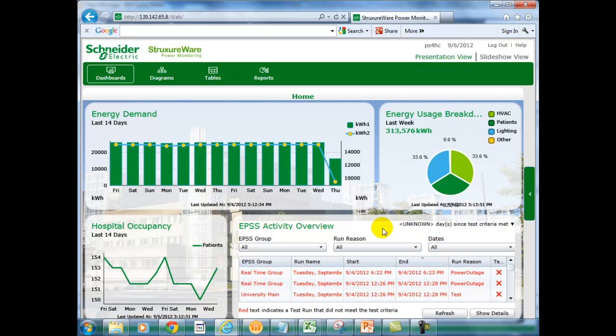What can hospitals and data centers do? Emergency system testing is often mandatory. Regulations like NFPA 99 require documented proof. Even if your state and local regulations don't absolutely require it, as a facility manager or ops person, you want the feel-good comfort factor of showing your boss proof that your systems are fully tested and ready to operate when called upon. That's where EPSS for StruxureWare comes to the party.